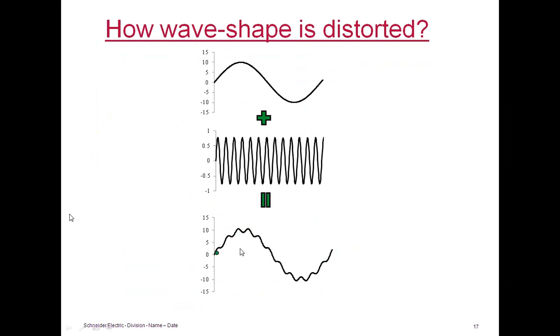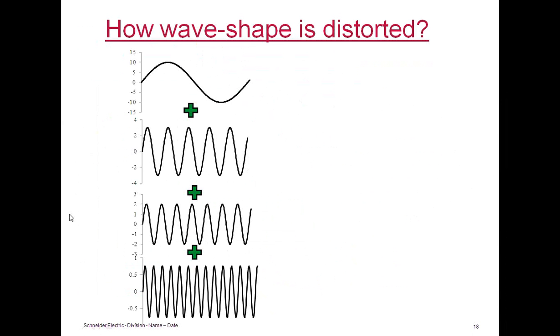Invariably, in any application, you can find the 5th, 7th and 11th harmonics; they are quite common. The 5th, 7th and 11th are a major contribution to the harmonic spectrum. So when you have these, you will have a waveform that is completely out of sine. Now imagine we design an induction motor or any equipment or machine assuming a pure sine wave, let's say 0.11 kV or any kilowatt rating, but we assume a pure sine wave to design the machine. If you apply a non-sine waveform, it cannot perform well. It will malfunction, it may fail, it may work with more stress, and so on and so forth.